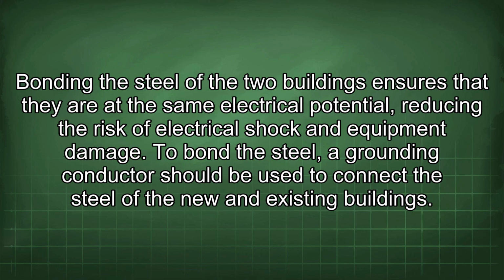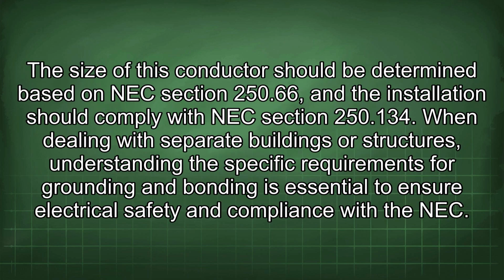To bond the steel, a grounding conductor should be used to connect the steel of the new and existing buildings. The size of this conductor should be determined based on NEC Section 250.66, and the installation should comply with NEC Section 250.134. When dealing with separate buildings or structures, understanding the specific requirements for grounding and bonding is essential to ensure electrical safety and compliance with the NEC.